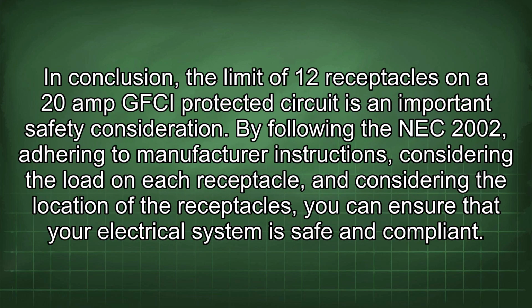In conclusion, the limit of 12 receptacles on a 20 amp GFCI protected circuit is an important safety consideration. By following the NEC 2002, adhering to manufacturer instructions, considering the load on each receptacle, and considering the location of the receptacles, you can ensure that your electrical system is safe and compliant.